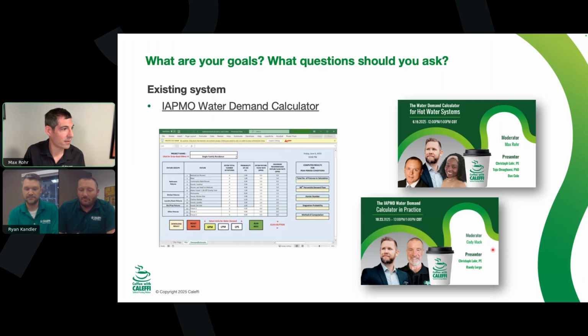Yeah, and I think when you hear numbers like that, like 70% less, the engineering and plumbing community thinks that's too good to be true. I don't trust that. But there's so much more data to show that even the outliers are still covered with this. Only in the extreme cases, and they had an example that hospitality can be tricky because some people will just leave the hot water on for 40 minutes to steam their clothes or something. That's not really normal use. We do have to accommodate for that, but even that could be still wildly less than the Hunter's curve.